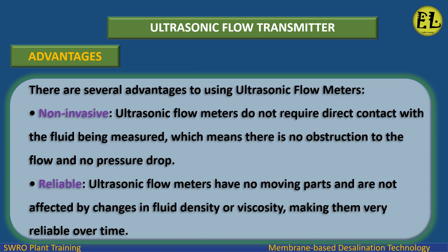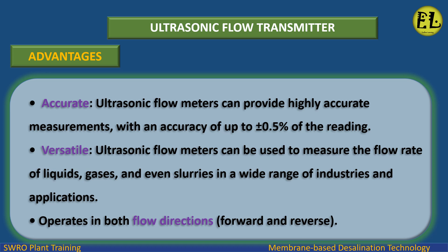Advantages of ultrasonic flow meters: Non-invasive — ultrasonic flow meters do not require direct contact with the fluid being measured, which means there is no obstruction to the flow and no pressure drop. Reliable — they have no moving parts and are not affected by changes in fluid density or viscosity, making them very reliable over time. Accurate — they can provide highly accurate measurements, with an accuracy of up to plus or minus 0.5% of the reading. Versatile — they can measure liquids, gases, and even slurries across a wide range of industries, and operate in both forward and reverse flow directions.